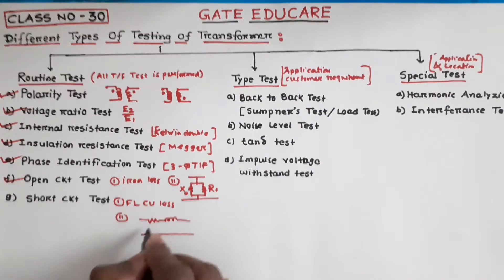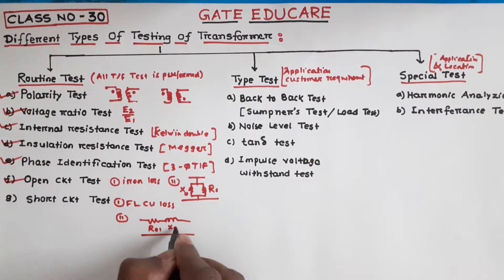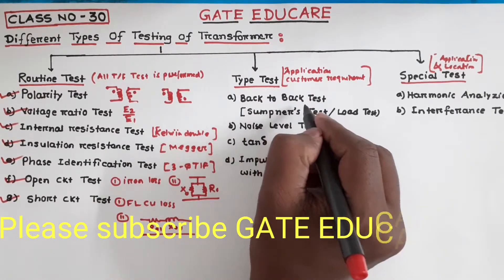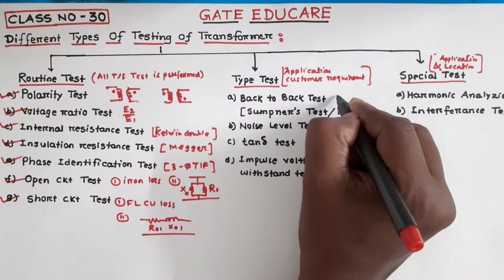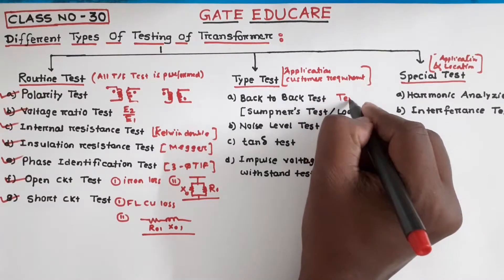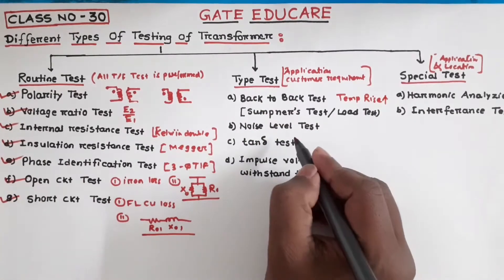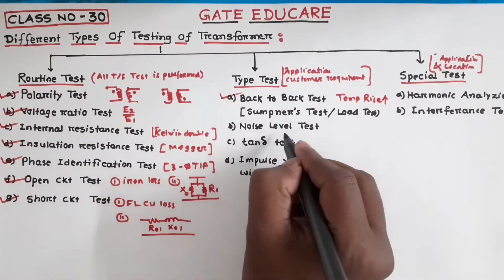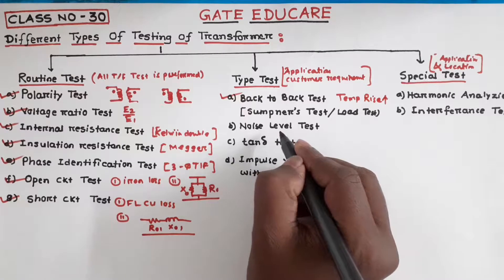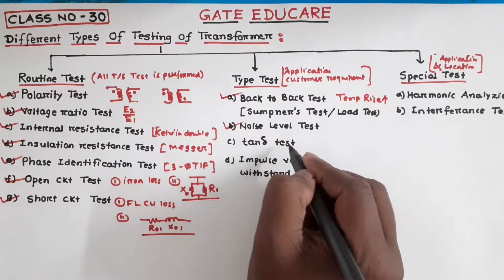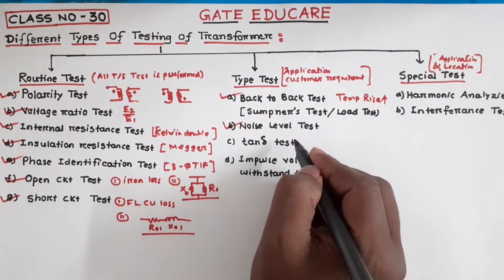Short circuit test: with the help of the short circuit test, generally full load copper loss and series branch parameters R01 and X01 are determined. Next, we will see the type test. The first type test is the back-to-back test. With the help of the back-to-back test, we determine the temperature rise of the transformer. Noise level test: with the help of the noise level test, the noise of the transformer is determined.